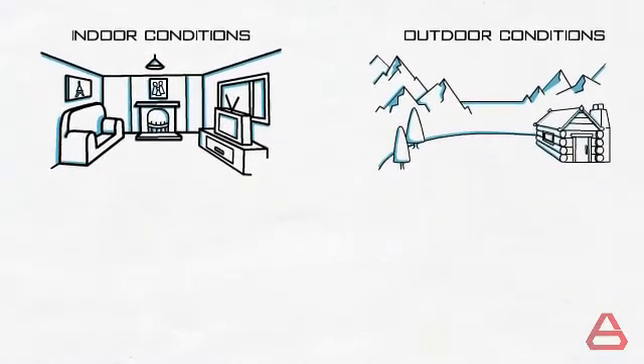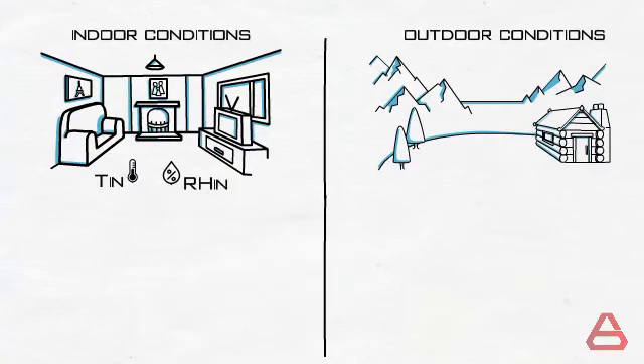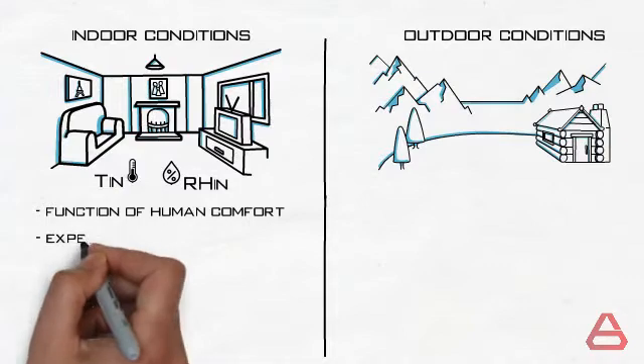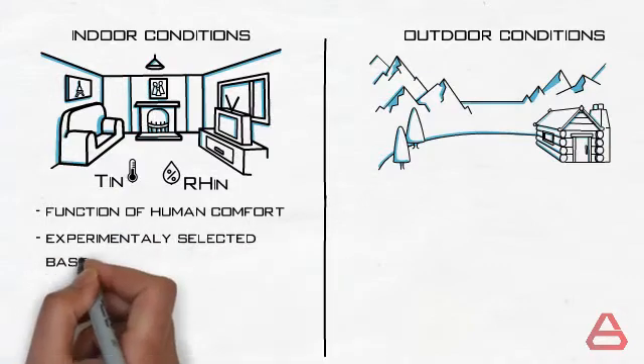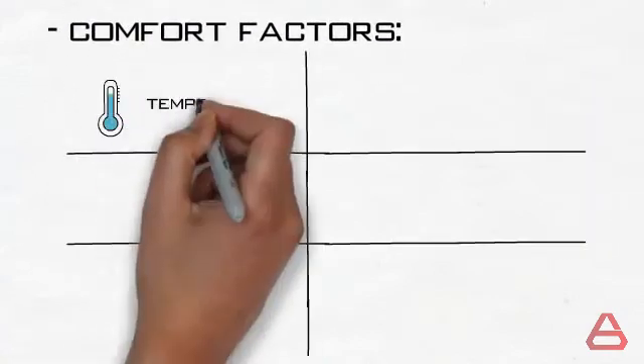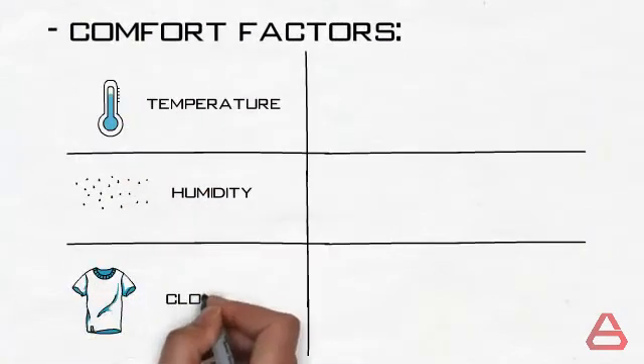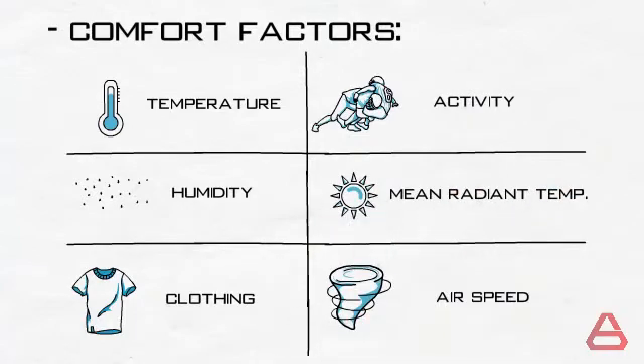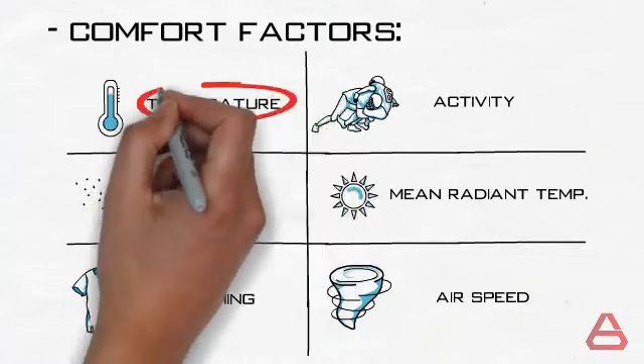The indoor conditions are indoor temperature and humidity, and are mainly a function of human comfort. They have been experimentally selected based on the aim of providing the best comfort for the dwellers of a certain building or space. Comfort is affected by multiple factors such as temperature, humidity, clothing, activity, mean radiant temperature, and airspeed. But the most practical parameters to control and those with the largest effect are temperature and humidity.